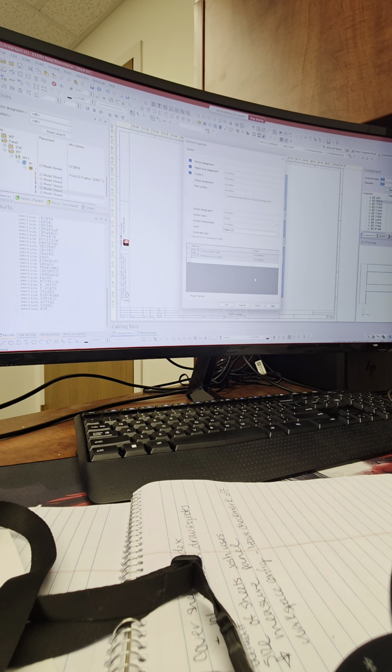Symbol properties, okay, and the part that you will be using to make them invisible will be this level option that you see as position 1. Everything that you ever draw in DTM, period, schematics and panel, by default it's this position 1, unless you want to put an object or a level somewhere else for different purposes. So if you scroll all the way down to the bottom of this list, there's something called construction layer, or even hidden panel plate, for example, that 254, second to last one. Click on that, 254, and click apply and OK.